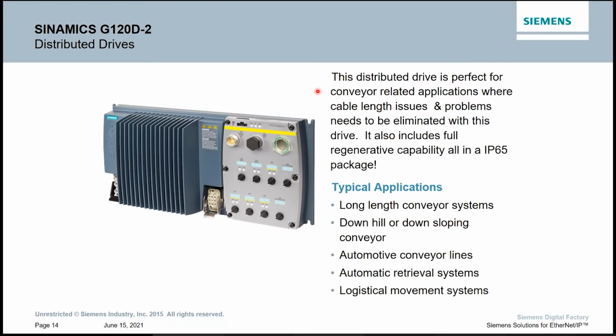G120D, I like to call this our Cadillac of distributed drives. You can tell it's safety. It has that nice yellow headband on. A lot of Siemens products will put a nice yellow headband to depict that it has safety on board. This is another modular design. You have the power module here, and you have the control unit here. This control unit unbolts, pops off.